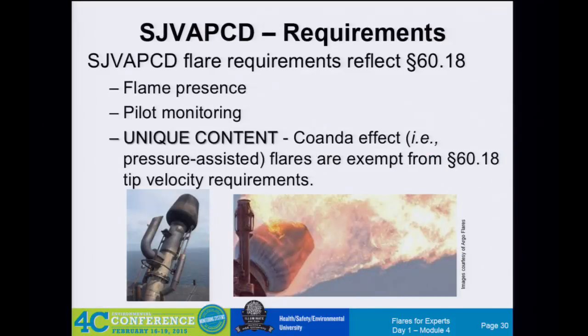Does the typical pressure-assisted flare tip have that design? Some do, some don't. There are a couple of companies that make this design. I think one company actually has one in this design that they sell and market. But nowadays the more common pressure-assisted type is the star pattern, with little arm branches and drilled holes or slots that allow air to come up from the bottom underneath. It just sucks it in.